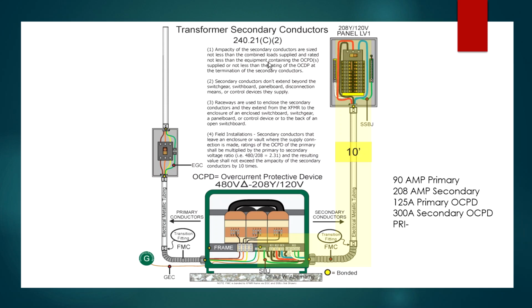That's all fine. Now, incidentally, if we had followed our base calculation and said that this was based on a 300 amp device, yes, it exceeds what the potential output of this transformer would be, but that doesn't necessarily mean the load actually exceeds it. I can always have a larger device as long as the load doesn't exceed it, and we have to provide a calculation accordingly. However, that would result in these conductors having to be rated for whatever this device was based on this rule as well. So these would be 350 kcmil. Or I guess I could parallel them as well and end up being smaller. But for a single one like this is shown, these would be 350. So you kind of see how that works, all based on whatever this device rating is. Okay, so that's the first one. Next, secondary conductors don't extend beyond the switchgear, switchboard, panelboard, disconnecting means, or control devices they supply.